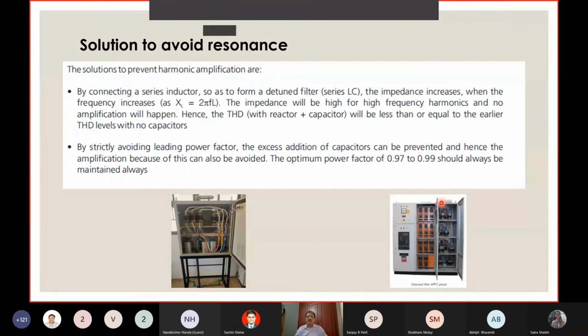And there should be sufficient cooling fans at the top. See, the most preferable is to have the cooling fans at the top rather than at the rear using louvers. You can have louvers, but the fan should be at the top because the hot air being lighter, it goes up, and it is always important to exhaust them through the fans at the top. Similarly, all the reactors should be on one side. The capacitors should not be placed here because capacitors are suitable only for 40 to 50 degrees centigrade. These temperatures can be 60 to 70 degrees centigrade, and capacitor life can be lost if they are in the path of the hot air. So these two are very important.